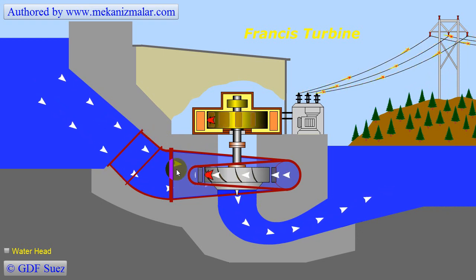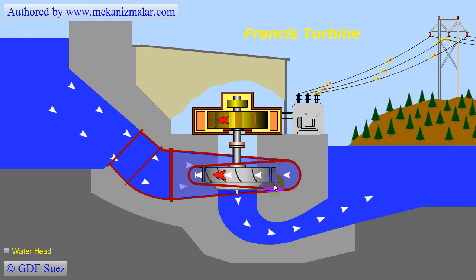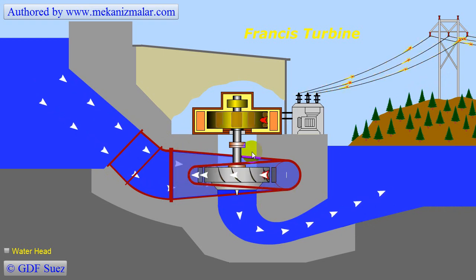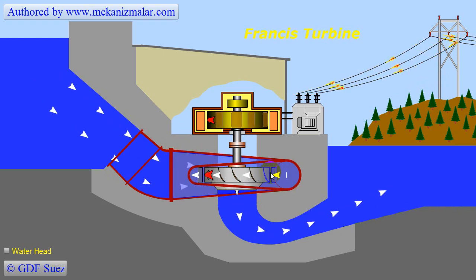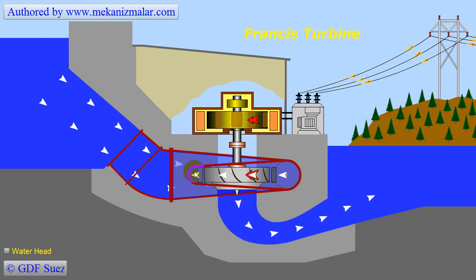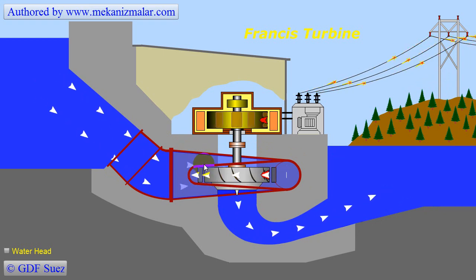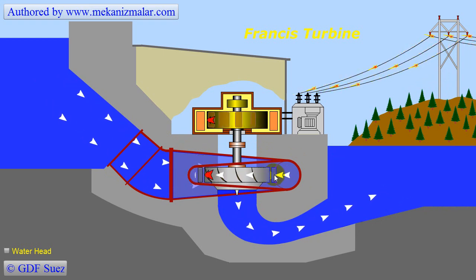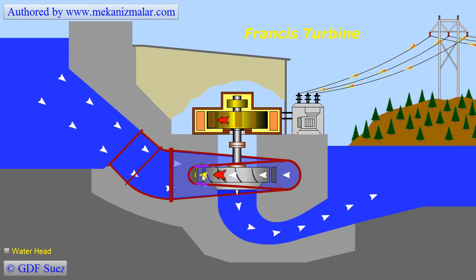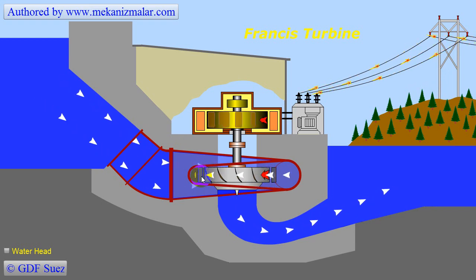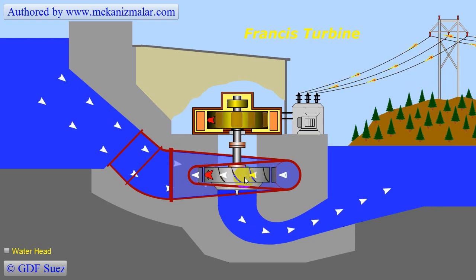The water coming from the penstock is transferred to the inlet scroll, which distributes the water equally around the wicket gates. Water then passes through the wicket gates, which control the amount of water passing through the turbine before reaching the runner.